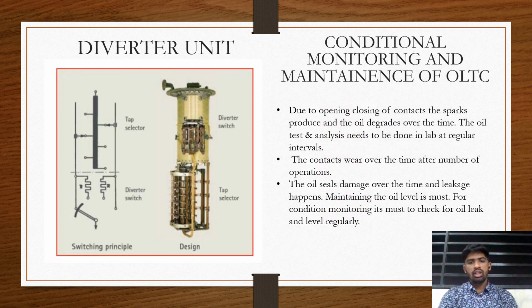Due to the frequent changing of taps, it has to be monitored and maintained properly. Because of this opening and closing of contacts, sparks are produced, due to which the oil degrades over time. This oil has to be tested, and analysis needs to be done in a lab at regular intervals. These contacts also wear over time after a number of operations. The oil seals get damaged over time, and leakage will definitely happen. Maintaining the oil level is a must. For condition monitoring, it is a must to check for oil leaks and levels regularly.